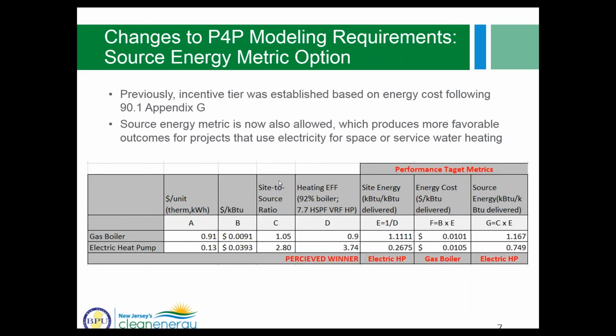So when we look at site to source energy conversions in column C, they are more favorable to electricity, and these conversions are based on the current EPA Energy Star Portfolio Manager conversions. So if, say, we're comparing energy consumed with a condensing gas boiler versus an electric heat pump, you can see here, depending on the performance target metric, site energy, source energy, or energy cost, either the gas boiler or the electric heat pump may come out as the winner, may be perceived as the more efficient system.